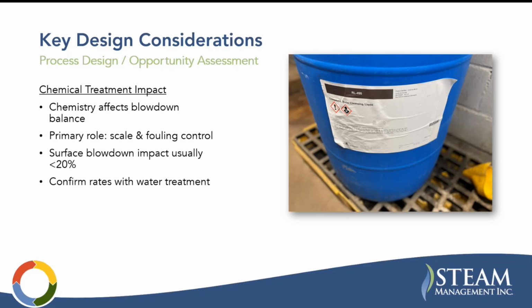And if someone's claiming that they reduce blowdown by 50% with using a certain chemical, it's probably paired with some other improvement in their blowdown procedure. Generally, I would say just your chemicals are going to reduce your blowdown less than 20%, because most of them are still going to be removed through your surface blowdown. The chemicals are going to help with scaling more than sinking dissolved solids to be handled out of bottom blowdown. That being said, chemical treatment is very important, and as we mentioned before, scaling is very bad in a boiler. So we want to make sure we do have a good chemical treatment program. The point here is that it may not significantly change your blowdown requirements.